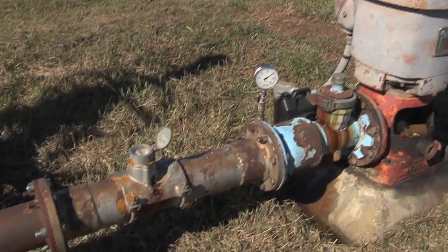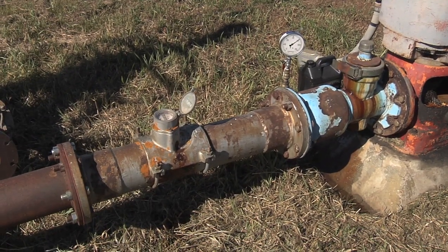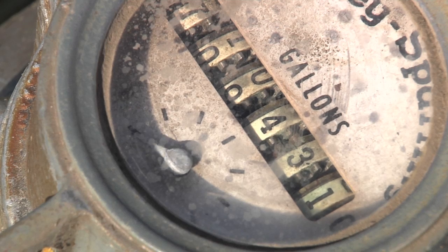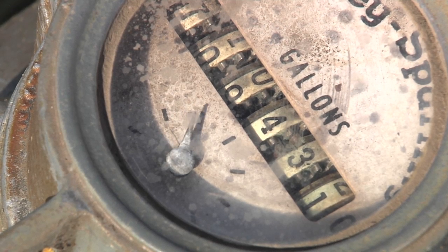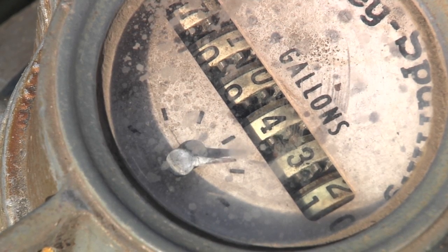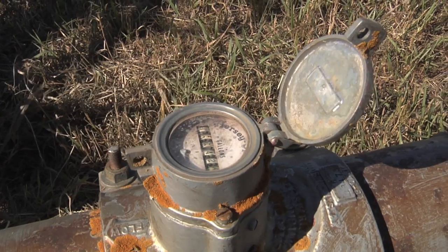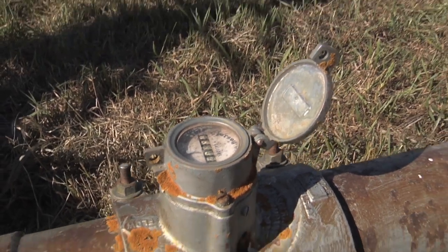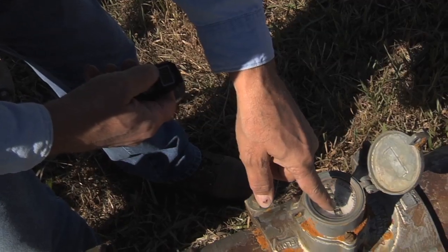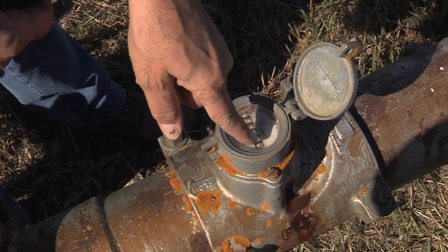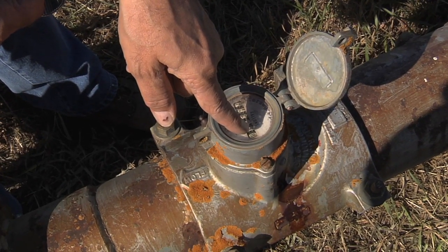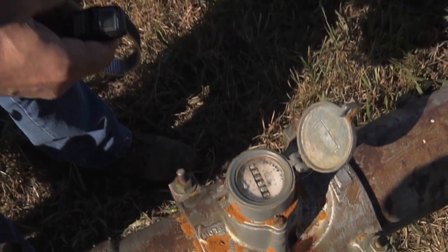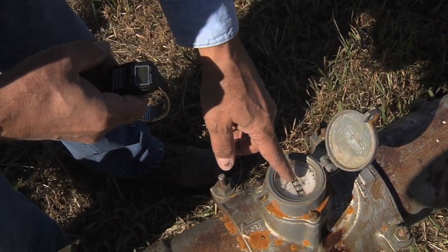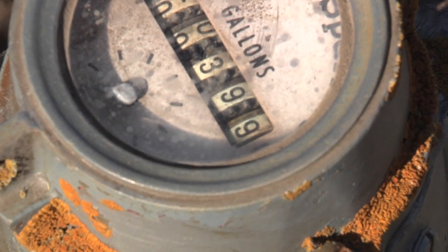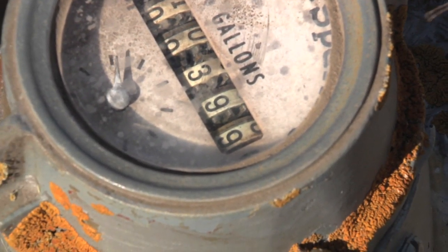Actually, the existing meter on this system appears to be turning. You can see the counter going around. So what we're going to do is time it to see how long it takes to pump 1,000 gallons. It should be about 1.5 minutes at 600 and some gallons a minute. When the 8 there gets even with the zeros, I'm going to start it and then time it when it shows 0.8, because every time it rolls over is 100 gallons, which is not unusual on a totalizer.